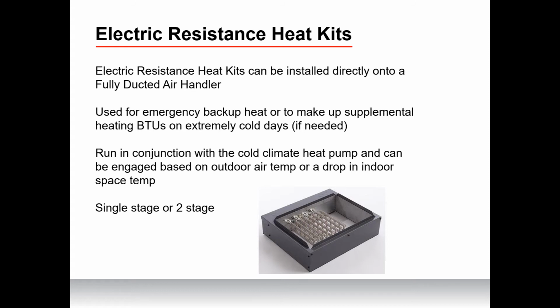They can be single stage or dual stage heat kits as well. So an important thing to remember with backup electric heat on an air source heat pump is that it's not necessarily one or the other, right? Especially with these heat kits that go on the multi-position air handler. If that cold climate heat pump can't keep up and it needs to engage a backup heat source, these electric resistance heat kits will engage and the air source heat pump will continue to operate as well. It will just work to make up those supplemental BTUs if that's the way you need it.